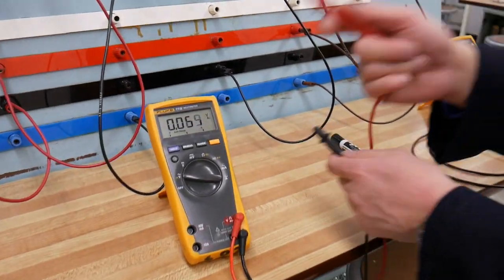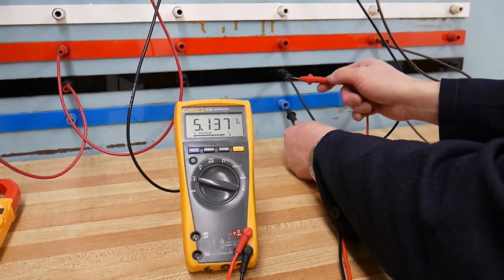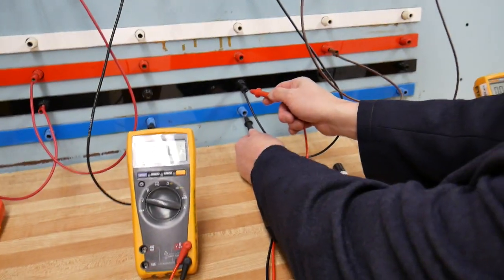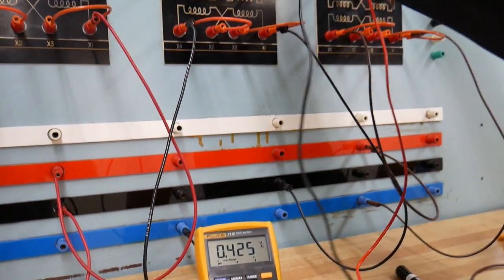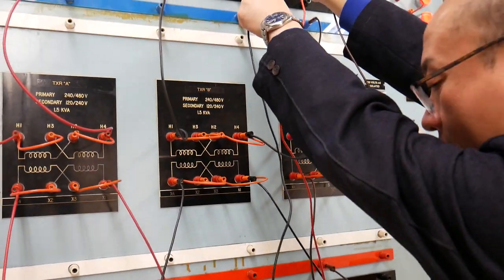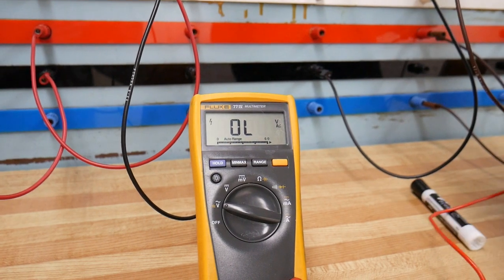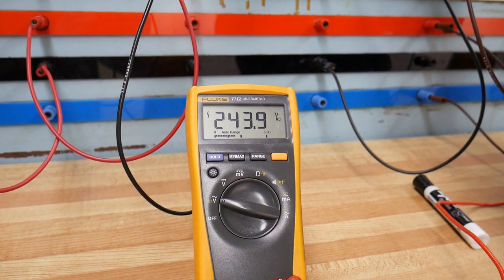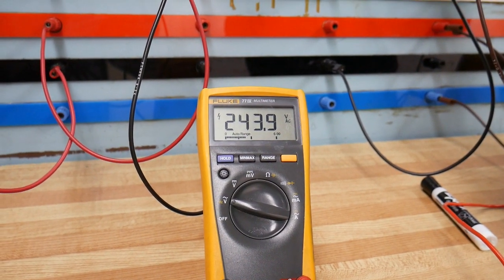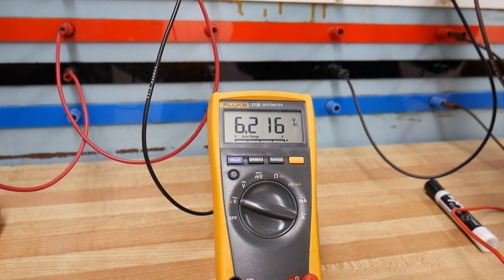Now I'm going to use this meter to measure my secondary line voltage, 120 volts. Now I'm going to measure the primary line voltage, 240 volts. Across each transformer I measure primary phase voltage, 240 volts, secondary phase voltage, 120 volts.